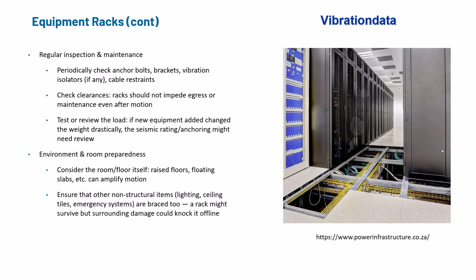For regular inspection and maintenance, periodically check anchor bolts, brackets, vibration isolators if any, and cable restraints. Check clearances—racks should not impede egress or maintenance even after motion. Test or review the load. If new equipment added changes the weight drastically, the seismic rating and anchoring might need to be reviewed.